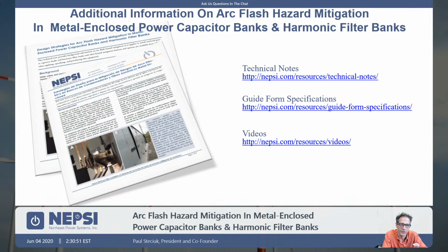But metal-enclosed systems are custom in nature. Each one is custom, and therefore each one should be type tested. Just like when you buy switchgear, okay, a piece of switchgear has been type tested. Well, each and every custom metal-enclosed cap bank and harmonic filter bank should be type tested. To say that you type tested one and then to change the design and not test the next is not proper. It should be a factory test.